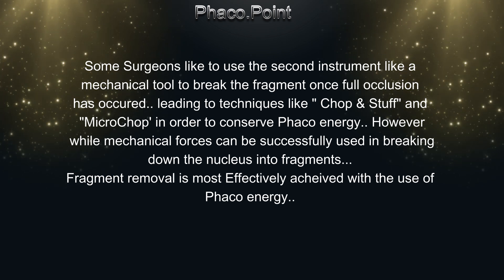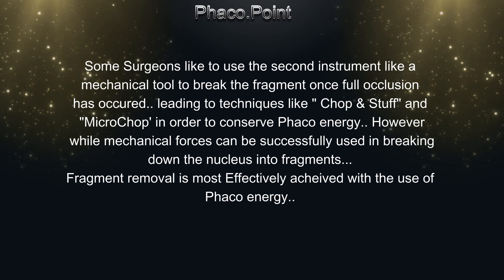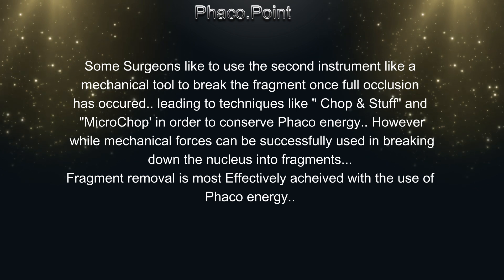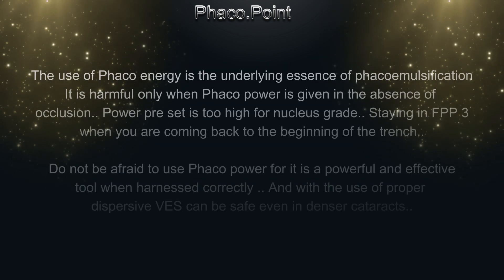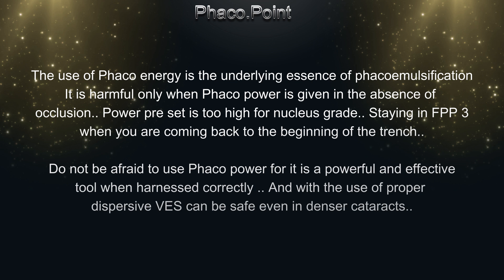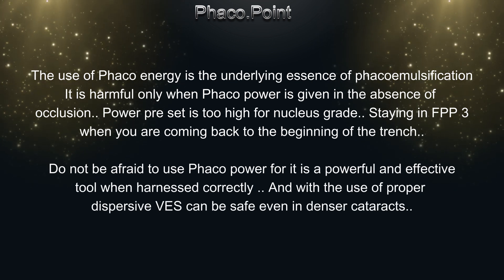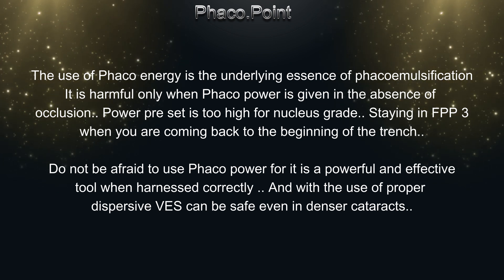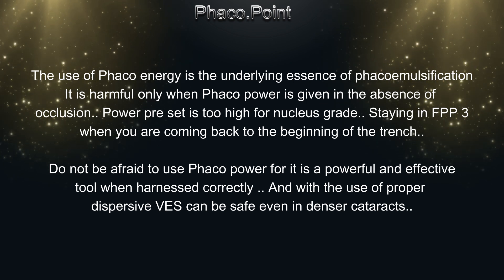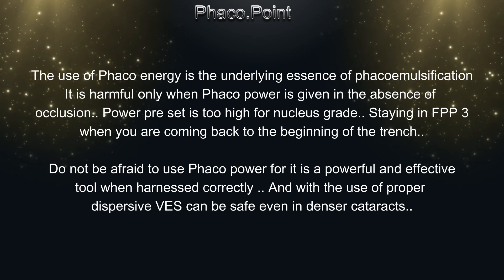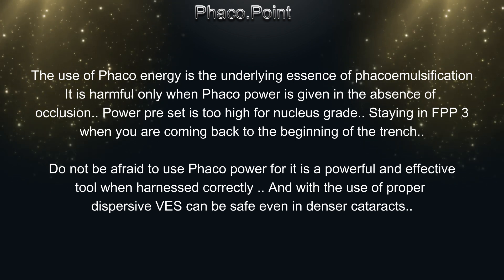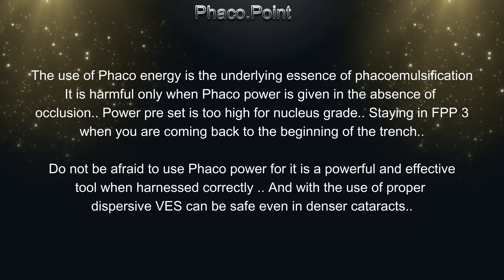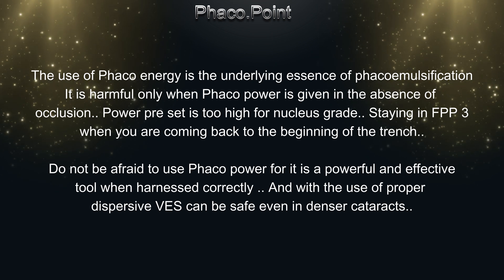However, while mechanical forces can be successfully used in breaking down the nucleus into fragments, fragment removal is most effectively achieved with the use of Phaco energy. The use of Phaco energy is the underlying essence of phacoemulsification. It is harmful only when phaco power is given in the absence of occlusion, when the power preset is too high for a nucleus grade, or when staying in foot pedal position 3 while coming back to the beginning of the trench. Do not be afraid to use phaco power — it is a powerful and effective tool when harnessed correctly, and with the use of proper dispersive viscoelastics, can be safe even in denser grades of cataract.